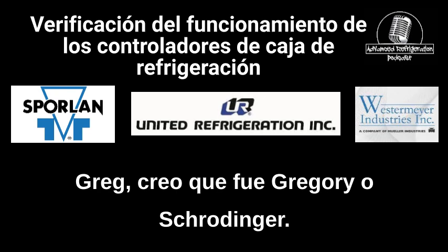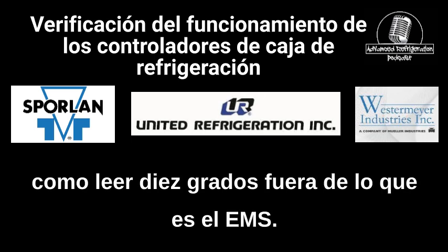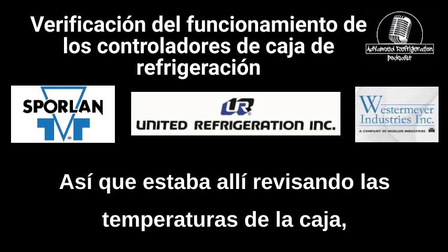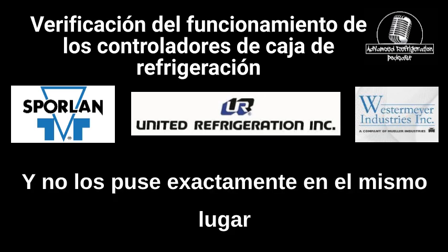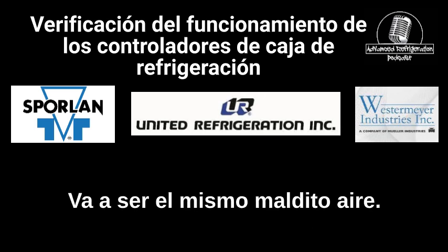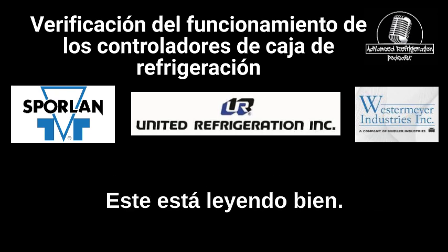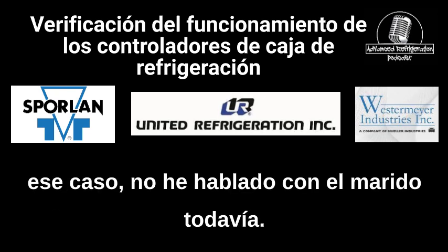So Greggy, I think it was either Greggy or Schrodinger, called me up and said, Brett, my probe is reading 10 degrees off from what the EMS is, and the EMS is even wrong. I'm like, that doesn't sound right. So I was there checking the case temperatures, and I jammed the probe up in one side and in the other side, and I didn't put them at the exact same spot, because I'm thinking, okay, the honeycomb is 4 inches wide, it's going to be the same air. And sure enough, I'm like, why is this reading off 10 degrees? This one's reading right. They told me this one was reading wrong, and it was because of that dead spot in that case. I haven't talked to Hussmann yet.